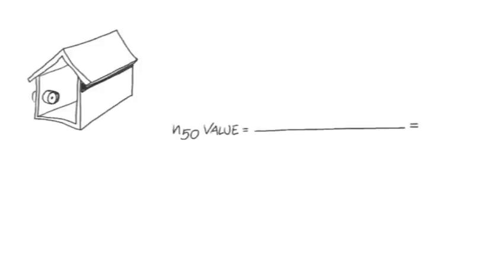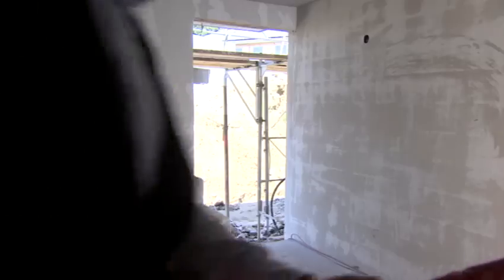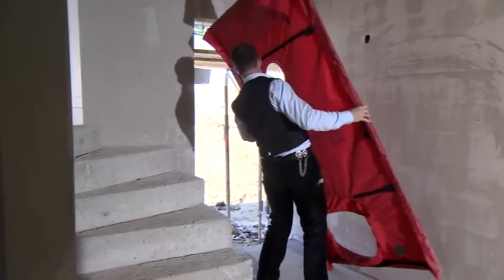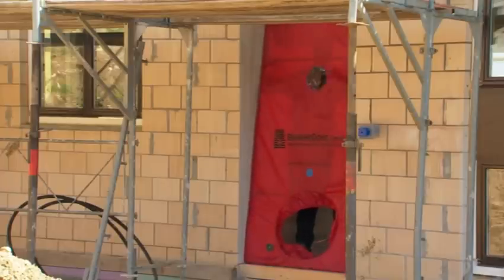The smaller the N50 value, the tighter the building. The most important information for the measurement is how much air is in the building. Our model house has an indoor air volume of 600 cubic metres. We include this value into the calculation formula: 600 cubic metres heated indoor air volume. For the measurement, a frame covered with an airtight membrane is fitted into the front door frame. All other openings of the building are closed.